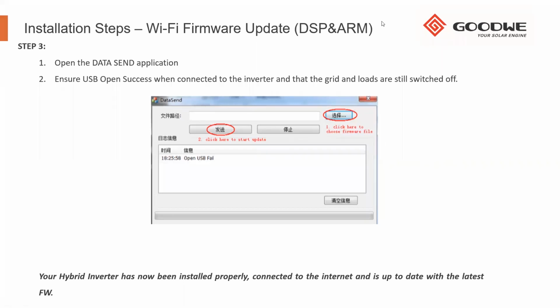So this is quite simple. You connect your USB into the inverter, you click here to choose your firmware file, and you click this button, and it will then update. Should you see the open USB fail, that means the inverter is not properly communicating with the computer. Very often you just pull the cable out, turn it around, pull it in again, and you might find then USB open success. So if it's connected, you just press this button. It will say data send, data send, data send, and you'll see a green bar run across. So once that's completed and you see data send complete, you can just close the application and data send is completed. If you would then like us to do the DSP remotely, you can then request this from your distributor or from our support website.